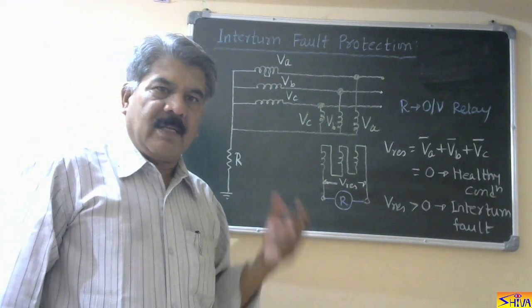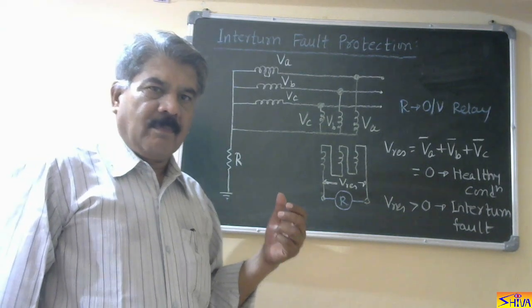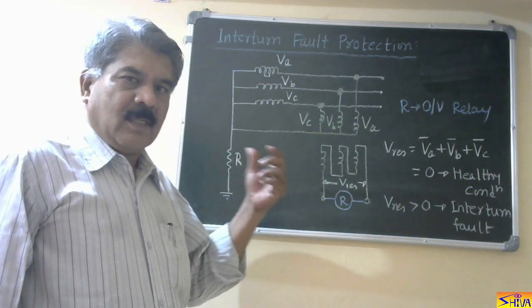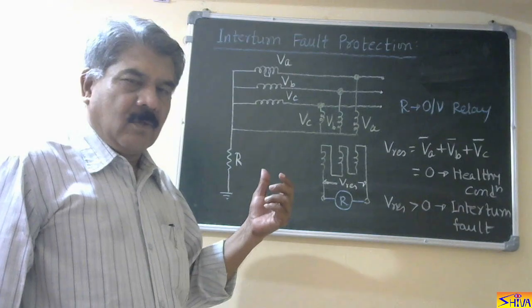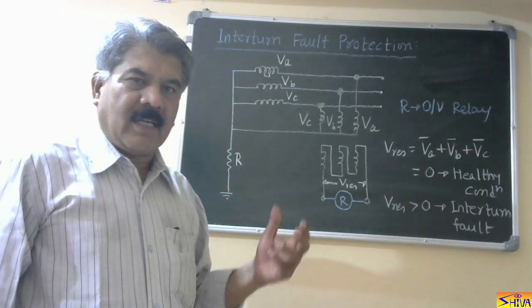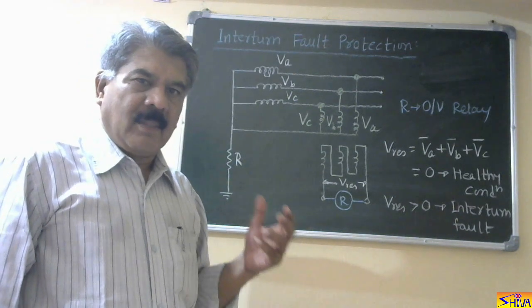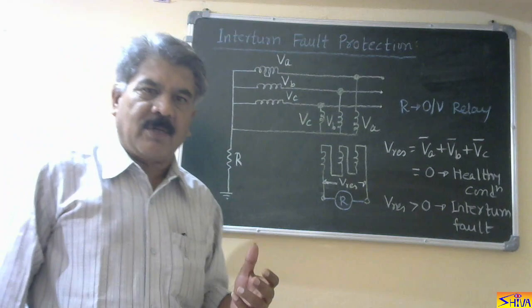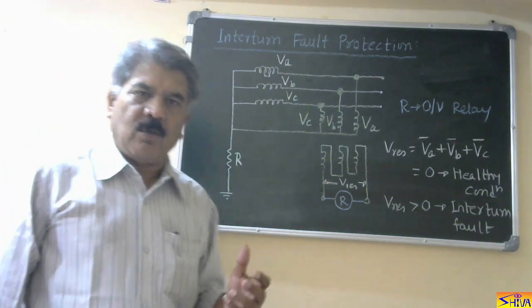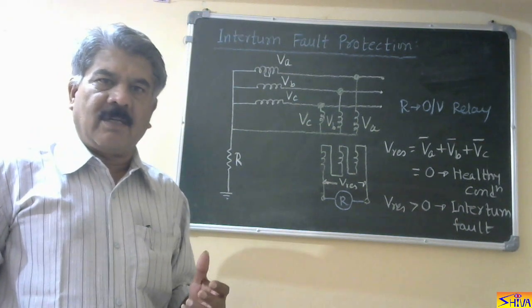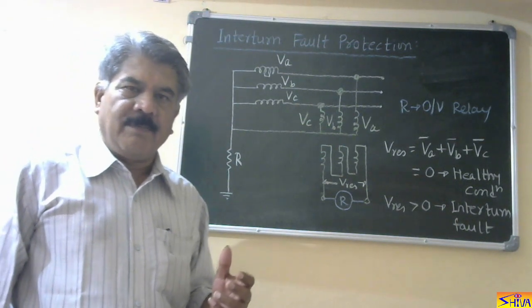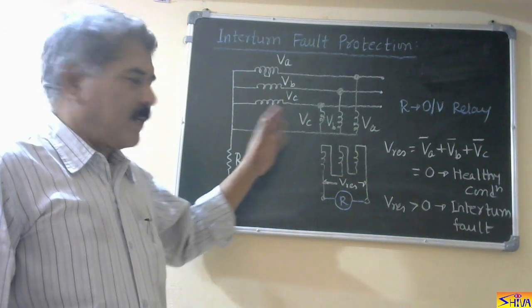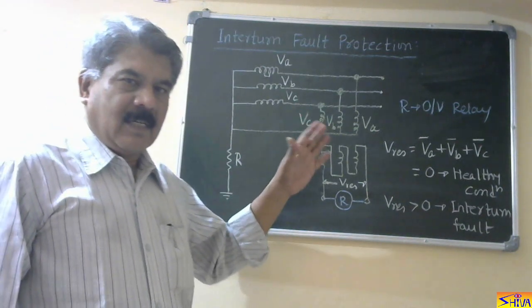There is no current difference in the CTs on both sides of the winding, so the differential current is zero. Therefore, the percentage differential relay — that is Merz-Price protection, also called longitudinal differential protection — is not able to provide protection against inter-turn faults.